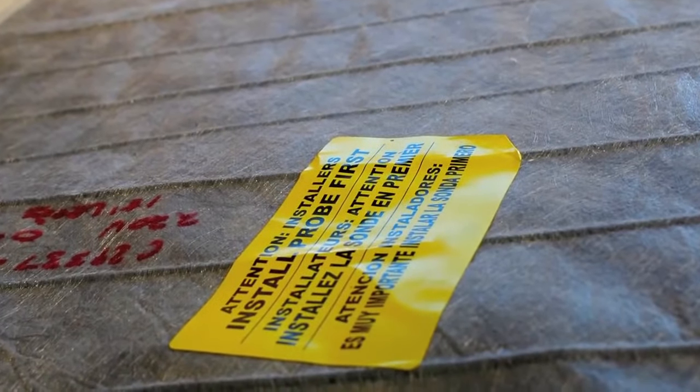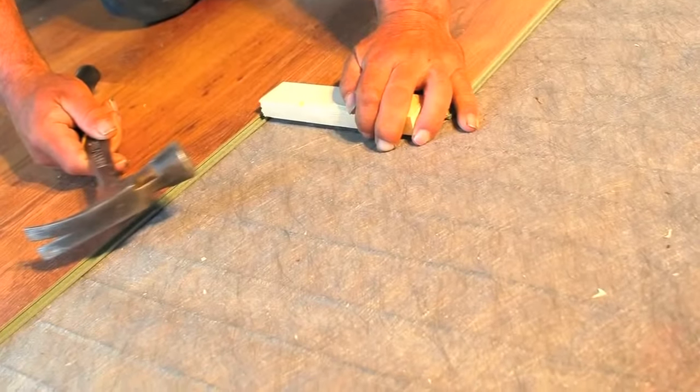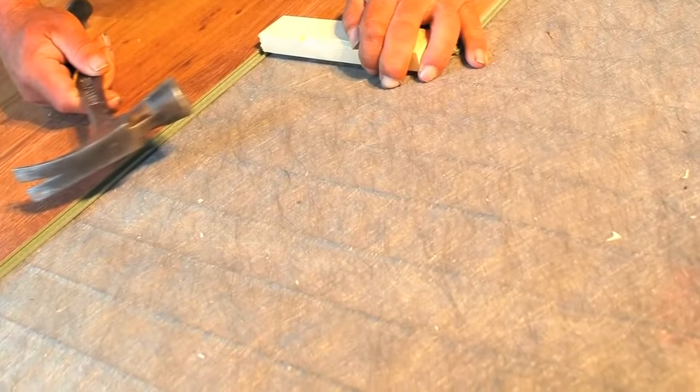Damaged wires and failure to heat is the biggest risk with electric in-floor heating systems, especially mat-style systems. Back in 2007, that's exactly what happened with one of my own building projects. It had a mat-style system installed in the floor, and less than one year after installation it failed with no warranty support from the manufacturer at all.